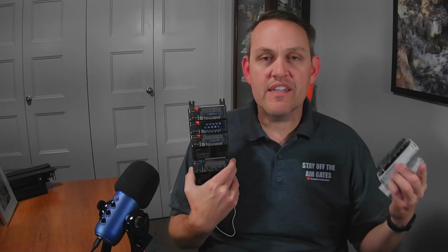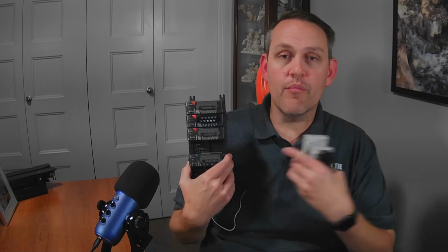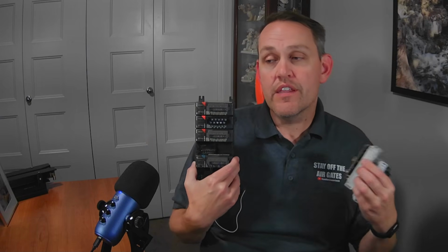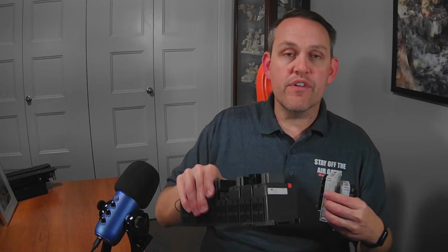Well, if I have brakes and things like that working 1.5 miles away, trying to do these exact same processes, that's a lot to get on that wire to come all the way back to here to make speedy decisions. Not to mention you have to worry about feedback and everything else on these circuits that might produce false signals and give you erroneous faults and errors while the ride is running. So they put a box near what you're working on, and they start giving you remote I/O. Now all those signals and commands I need, I just take power from my main control cabinet 1 mile away, and I run whatever voltage I might need out to that cabinet, and then I distribute it inside of that cabinet to these guys.